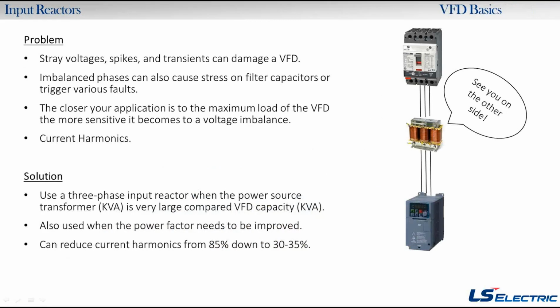So, input reactor. An input reactor is going to go between your power supply and the drive, and what that's going to do is help if you have issues like stray voltages, dirty power, voltage spikes, or transients. Those could all damage the VFD. Or if you have any kind of phase imbalance, that could cause stress on the filter capacitors, which are on the input of the drive. We didn't talk about them too much, but they're there to protect the input. Or if you have current harmonic issues.